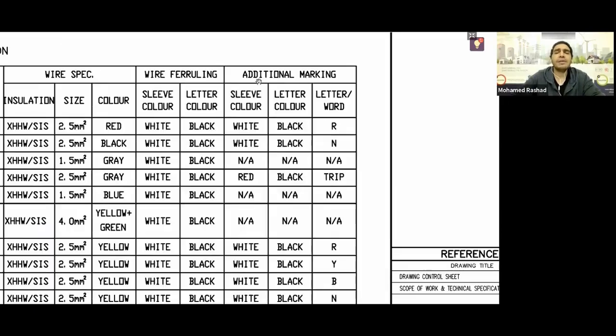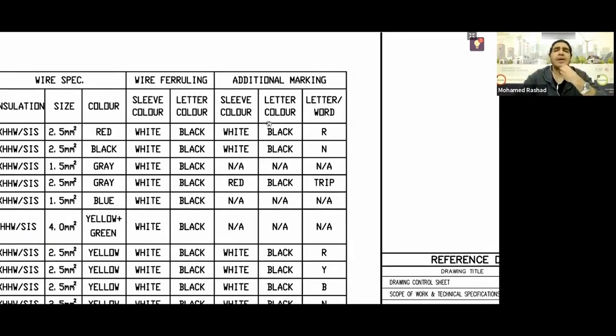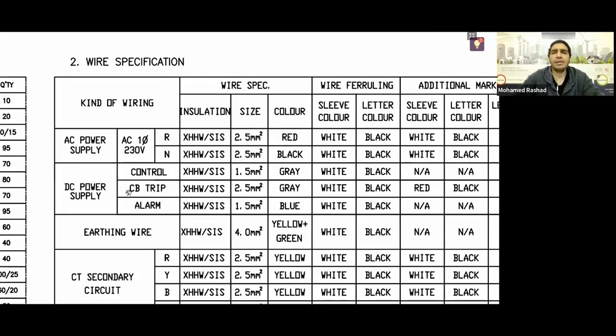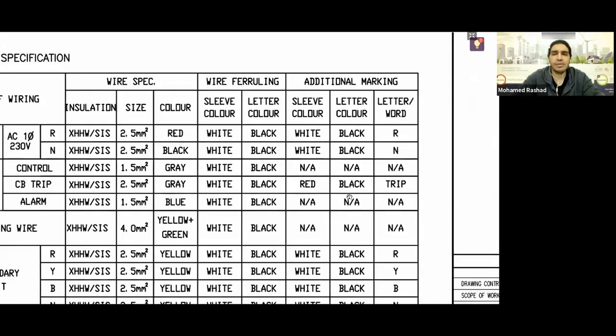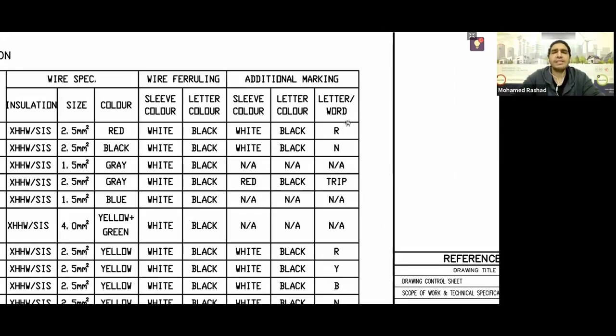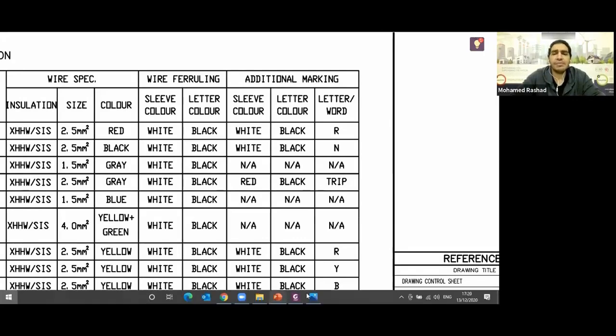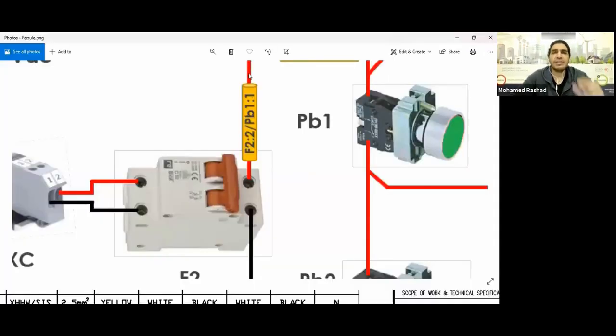You also have something called additional marking. This usually doesn't have anything special except what's related to the direct trip. Concerning the circuit breaker trip, you'll find a letter or word written, which is 'trip'. Regarding AC, it tells you R and N. This means you have additional plastic pieces placed here, like a ferrule, with R, N, and the letter T or word 'trip' written on them, so you understand which wire is used for tripping and which is used in the AC. This is additional marking, something extra that clarifies things for you or conveys information in another way.